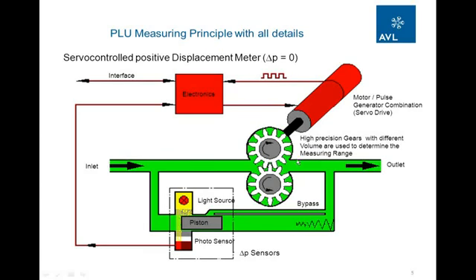If we do not have a pressure drop here, then there is no reason for the fuel to leak anywhere, and that means this measuring principle is independent of changes in density, viscosity and temperature. And here with this piston sensing part in the bypass, we have a light source, we have a piston, and we have a photosensor. And the position of this piston is proportional to the fuel flow.